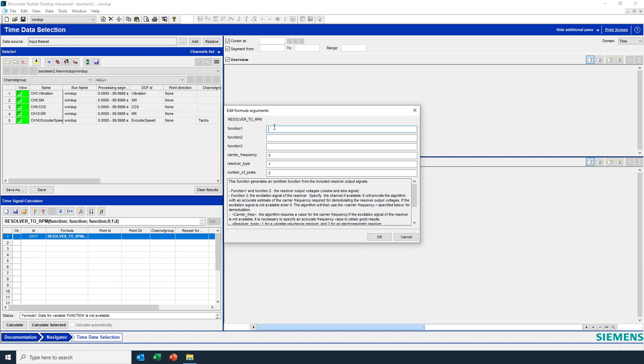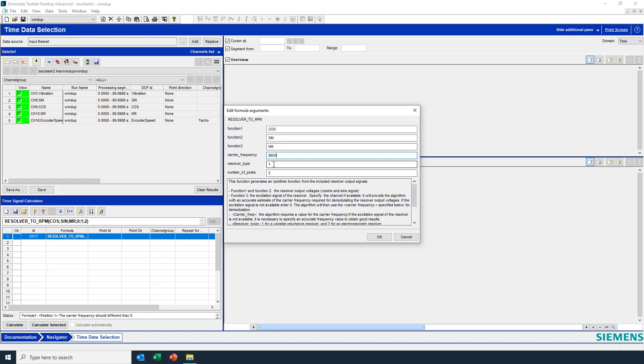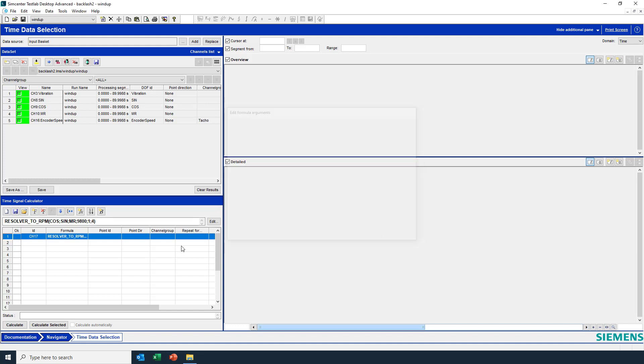Under function one and function two I need to enter the cosine and sine waves. So I'll put in COS here because I can use the ID if I want. Here I put in the excitation voltage MR. Because I have the excitation voltage this isn't meaningful, but I could put in the carrier frequency. And this is a variable reluctance resolver with four poles. I'll hit OK here.